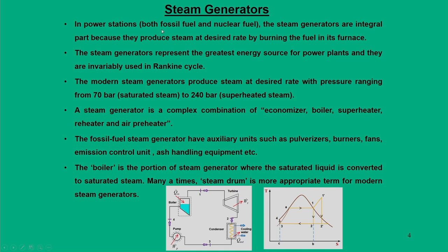In power stations that operate mainly on fossil fuel and nuclear fuel, the steam generator is an integral part because its main aim is to produce steam at a desired rate by burning the fuel in its furnace. Steam generators represent a greater source of energy for power plants and they invariably use the Rankine cycle. For most modern power plants, they operate close to 240 bar for superheated steam and 70 bar for saturated steam. The steam generator involves complex combinations of components, mainly heat exchangers: economizer, boiler, superheater, reheater, and air preheater.